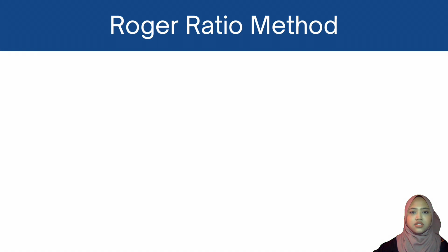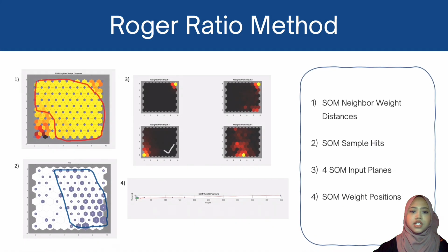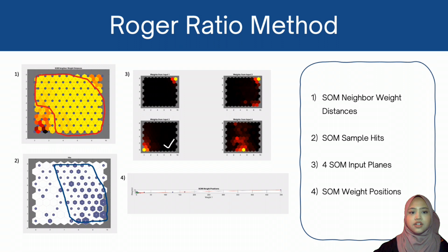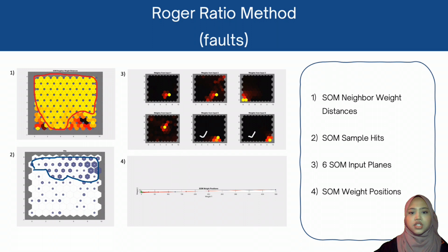For the first method, the Rogers ratio method. From the visualization map of ratio analysis, the first map shows a majority of yellow connections, which indicates that it is highly connected. At the bottom left, some red connections show the different input and weight connection. For SOM input planes correlating with SOM sample hits, the third input plane shows a similar weight. For fault analysis, in SOM input planes, the input for faults T2 and T3 shows a similar map. Conclude that the faults observed from Rogers ratio are local to severe overheating.